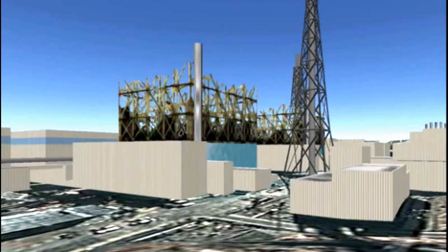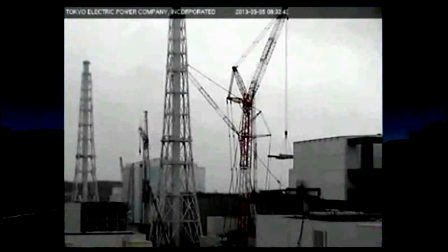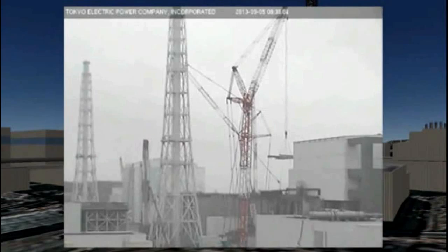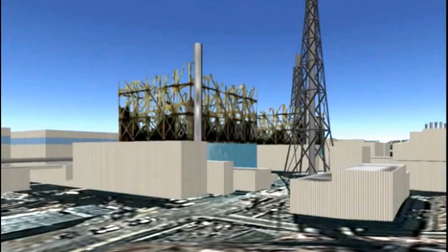Unit 3 is so badly damaged that they cannot move the nuclear fuel in the traditional way — the structure won't handle the extra weight of a heavy crane inside it. What they're doing now is still removing rubble, and those cranes are being moved remotely because the radiation exposures around these buildings are so high. Inside that building is essentially a no-man's land.